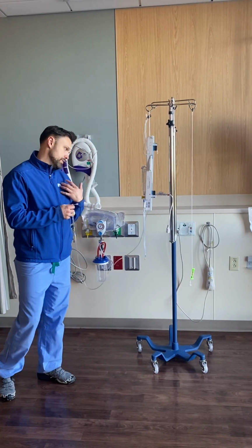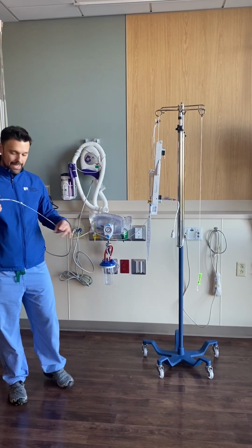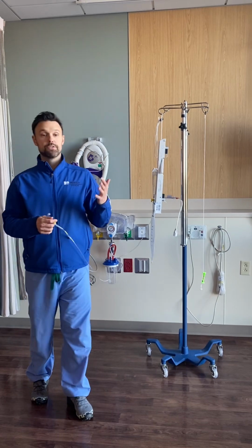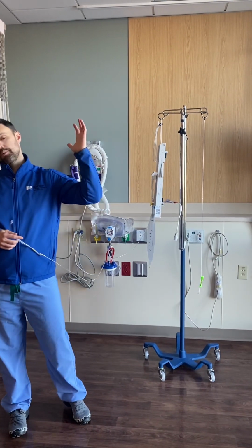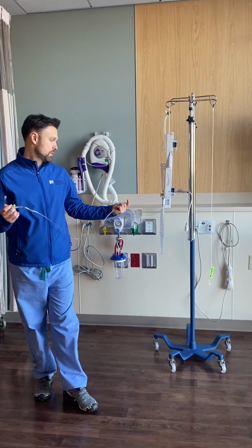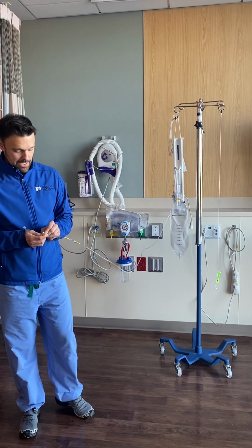And what you're trying to do is just basically make sure that there's no air bubbles in the system. If you see any air whatsoever, then you might need to flush it more, because any air that gets potentially trapped in there can cause an abnormal ICP reading, or it can cause the inability of flow of spinal fluid out. I'll let Terry go over the specifics of that.